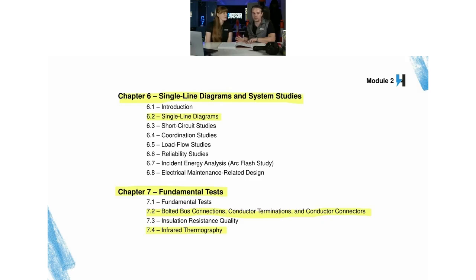Now, you might be familiar with the NFPA 70E 130.5G, which states that the arc flash study or incident energy analysis shall be reviewed no later than 5 years, right? Mm-hmm. Now you have all these other studies that you must complete and review for accuracy at intervals not to exceed 5 years. So that's a big jump right there. Yeah. Got to make sure that you keep those up to date. And that's for, again, equipment reliability and personnel safety. Right. Depending on what the study is.